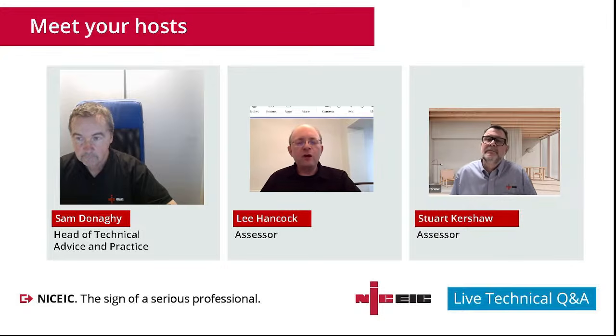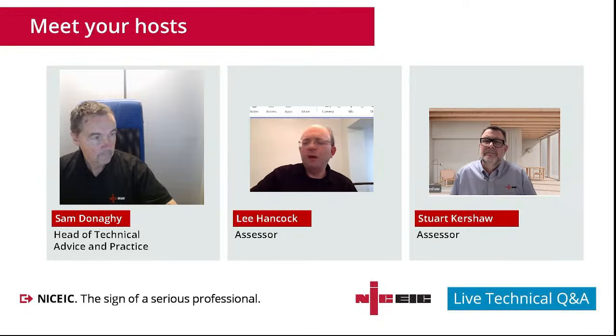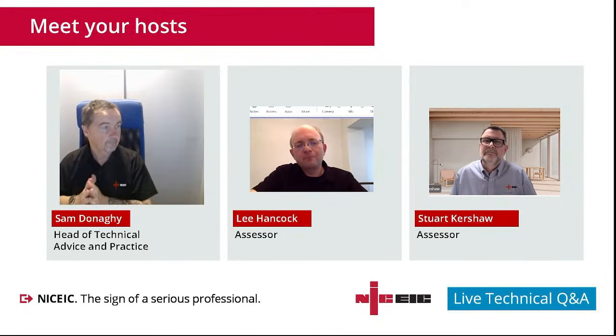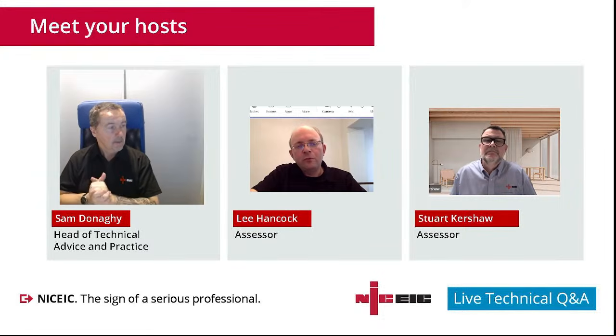And if the readings aren't accurately recorded, when we go back in 5 years, 10 years, or whatever duration you specified, we can actually see that the reading's falling. If we just put down a uniform 100 megohms down the certificate, that might not be accurate. Yeah. So be clear, be concise with what you write on the certificate. Accuracy on this is key, especially if we're monitoring a situation. Write down what the meter says.